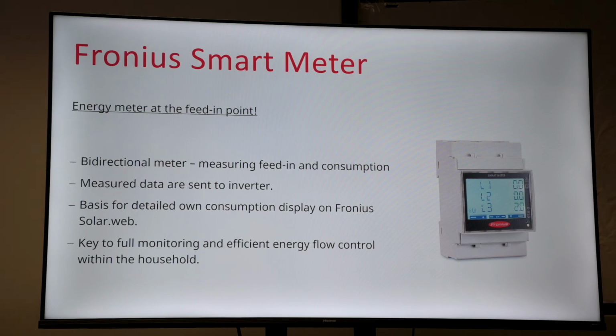You can do full monitoring on the meter itself, as well as having separate meters for the system. So if you have one main grid meter for the feeding point, and let's say you have 3 different tenants that you want to monitor individually to see what their consumption loads is, you can have 3 separate smart meters on the system, which will be fully displayed in SolarWeb itself.